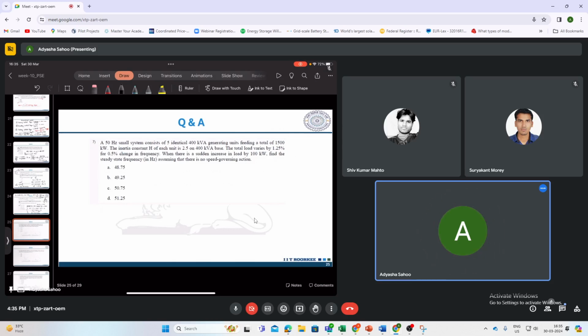So first, here it is given that there are 5 identical 400 kVA units, which means that your base MVA is the number of generating units, 5, into 400, the rating of each. So that will give us 20 MVA, 2 MVA, not 20. Okay, now from here I can calculate first D.